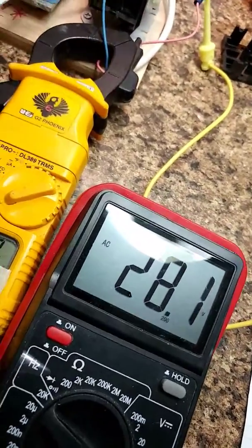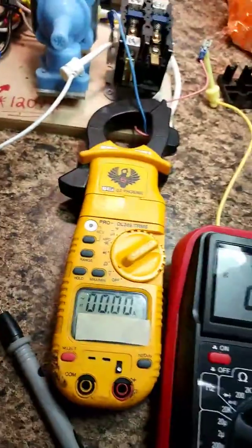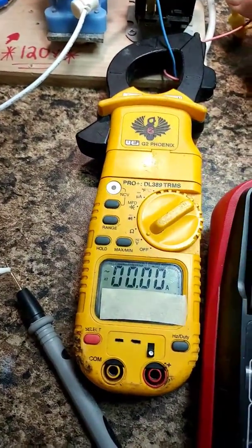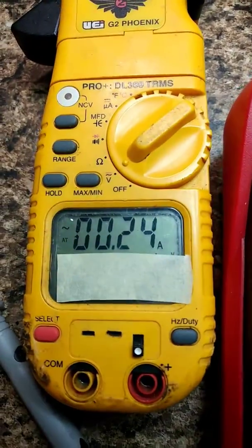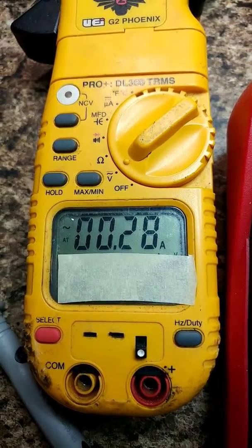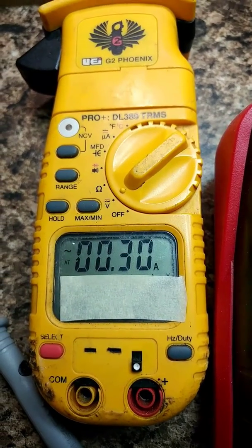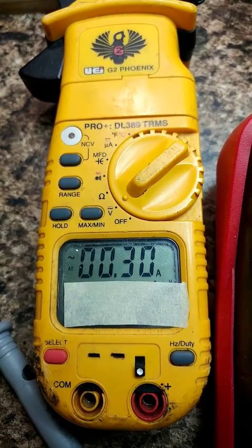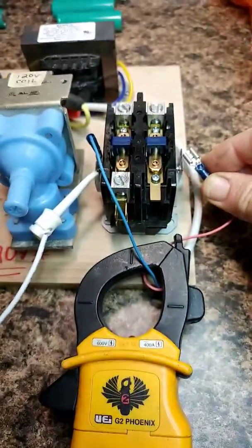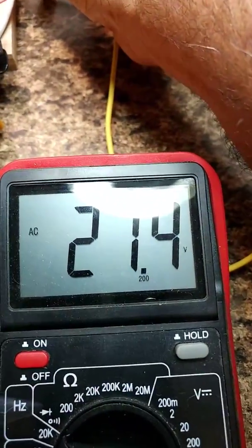So what we're going to do is I'm just going to show you what the amperage is on this coil when I energize it. So the contactor is energized, and we're pulling about 0.28 to 0.29 amps. So that's what we're pulling, about 0.3 when that coil is energized. And our voltage dropped to 21.4.